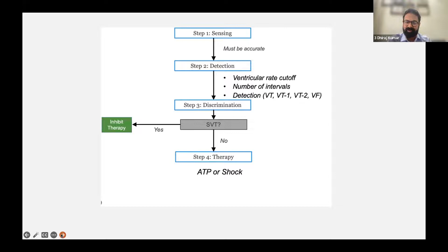If it is a VT, then it goes on to deliver therapy in the form of anti-tachycardia pacing, that is 20 to 30 millisecond cycle length lesser than the VT. Of course, we decide the therapy. There are two types of anti-tachycardia pacing: burst pacing and ramp pacing. In ramp pacing, each progressive paced beat is at a cycle length which is shorter, so the cycle length becomes shorter and shorter. We'll have an example to show that. And finally, if anti-tachycardia pacing doesn't work, there will be a shock delivery. Okay, so these are the four steps.